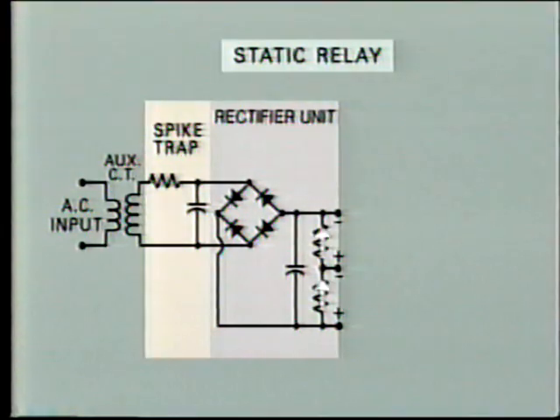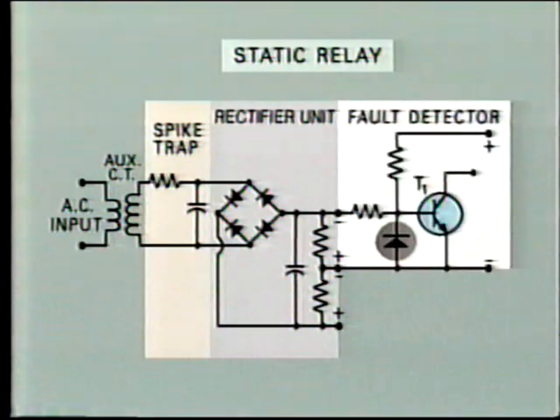The DC current circulates through this resistance, which in turn sets up a corresponding voltage. Note the polarity. It is positive at the bottom terminal and negative at the top terminal, while the tapped terminal is somewhere between the two. The fault detector unit is connected to the rectifier unit like this.